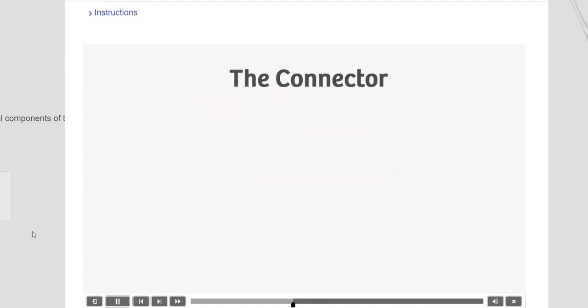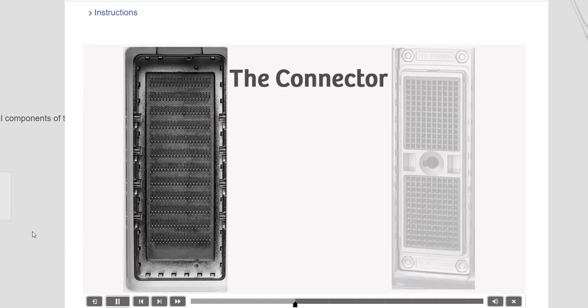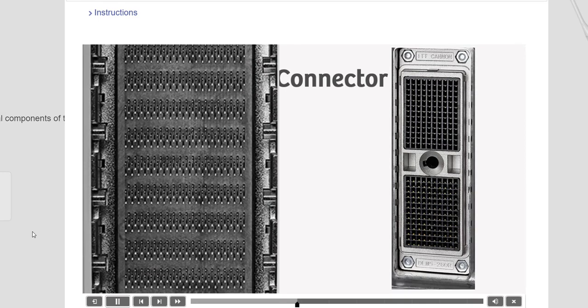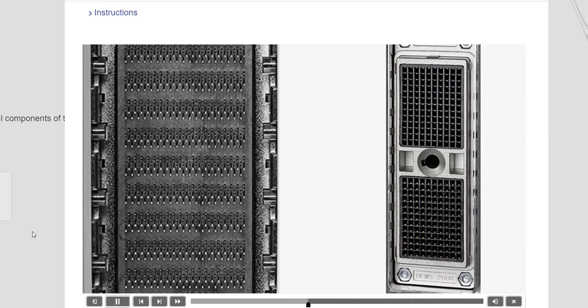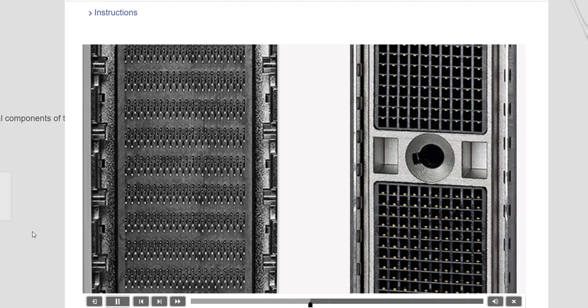There are two types of connector ports, pinless type and pin types. Pinless connector ports mate the transducers to the system without pins. Advancements in pinless coupling reduce damage from transducer installation and reduce image artifact. In the pin-type connectors, damage can occur to the pod where the transducer interfaces with the ultrasound system. With pin-type connectors, take care to properly align the delicate connector pins to the system interface before locking the transducer in place.